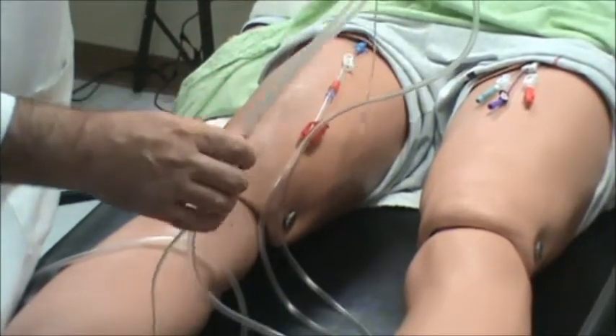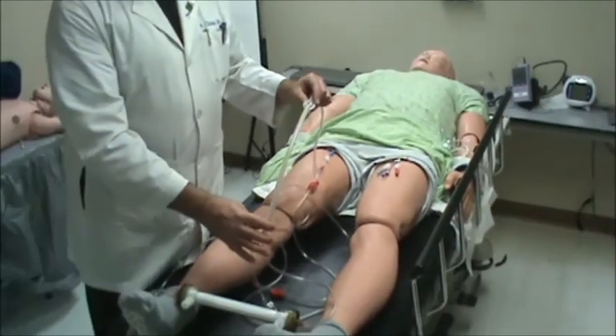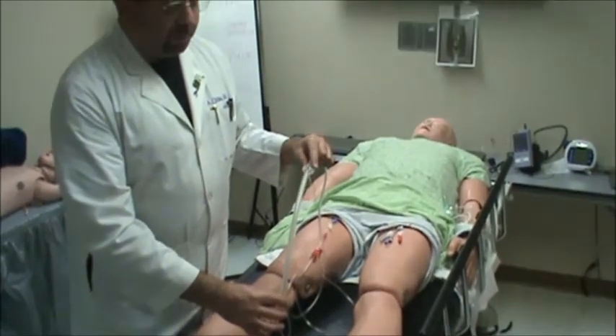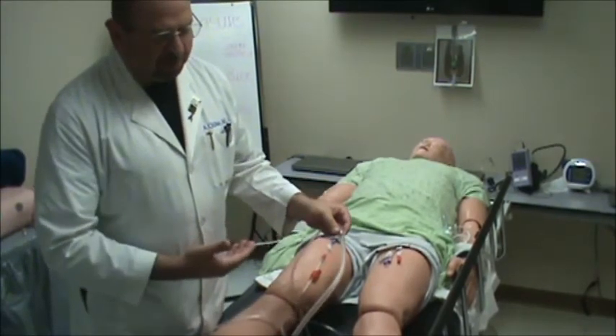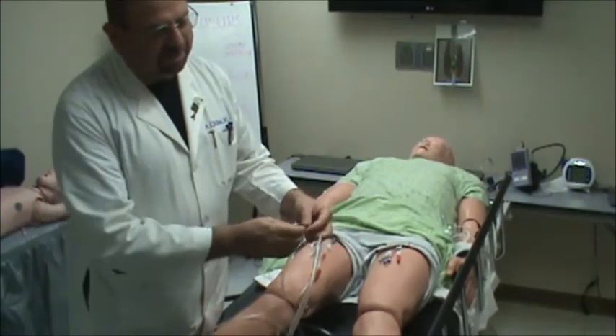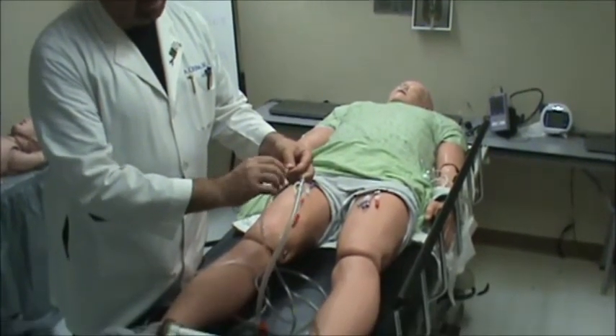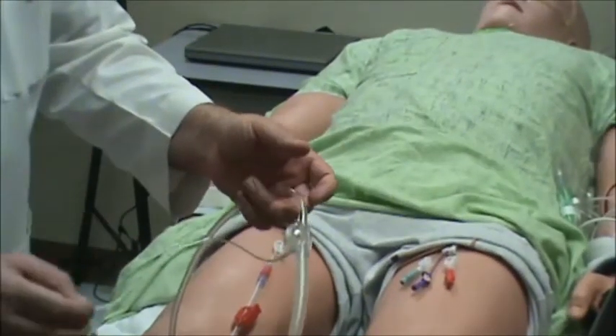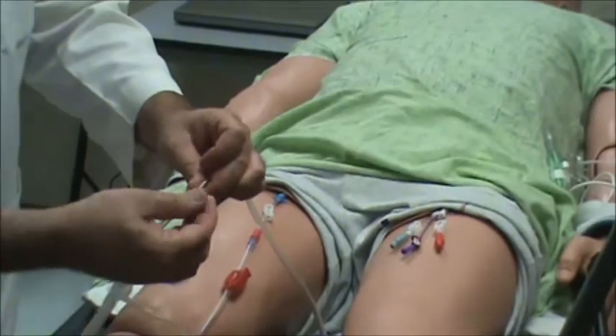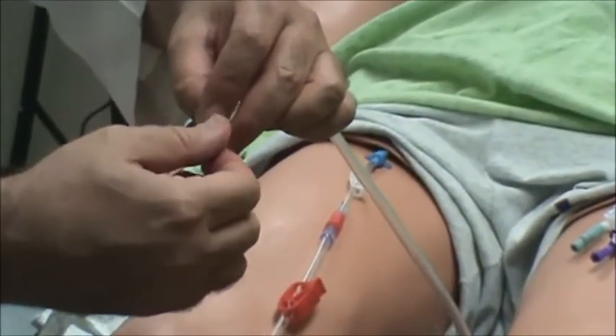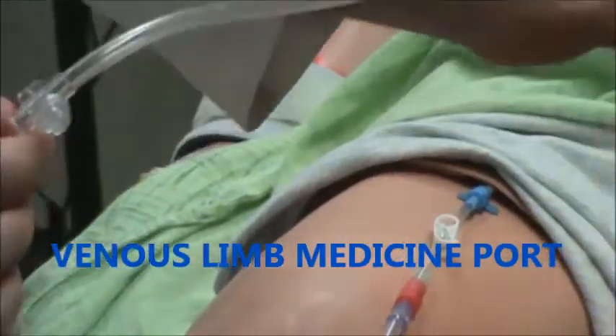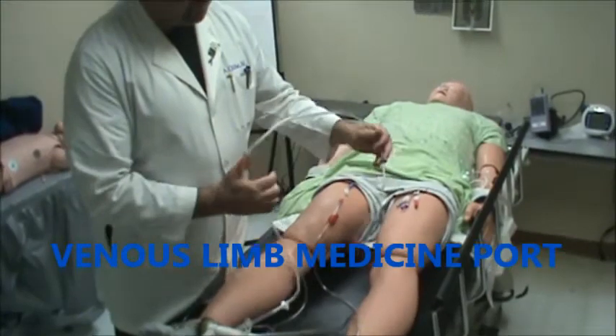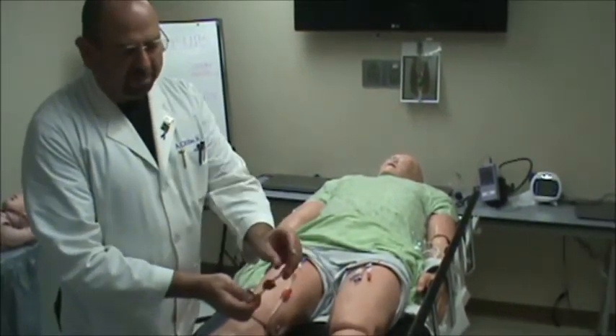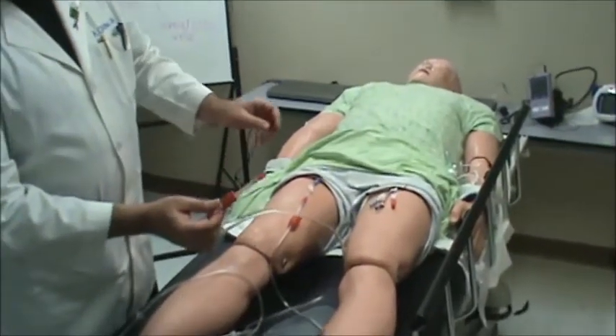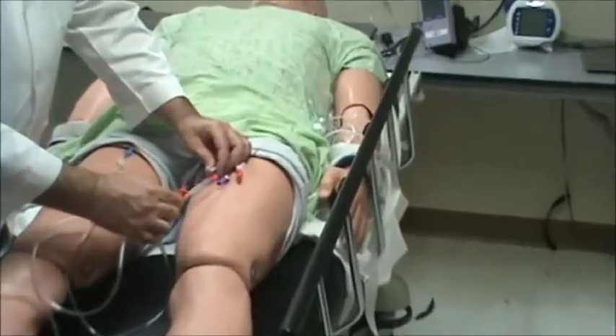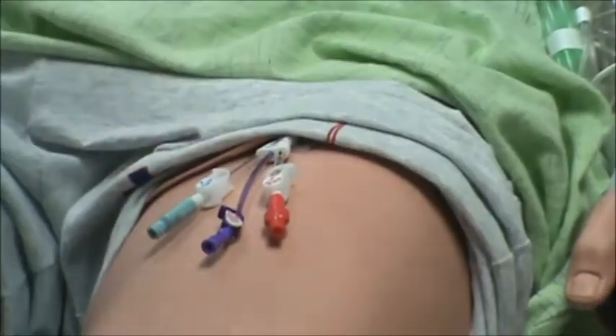Again, this big segment is called the pump segment, and this tubing is not designed for CAVH, so we will ignore this. Again, this is the pressure monitor or pressure sensor. Sometimes it's nice to have a syringe or a cap at the end and put a tape around it so nobody will access it nor use it. Again, this is also a medicine port where you can use Luer lock technology to insert it and tighten it and get access into the main circulation. And again, this is the patient end of the tubing, which is a male Luer lock, and here's a clamp, and then it can be inserted in any of these ports, because all of them are venous ports, even though one of them is red.